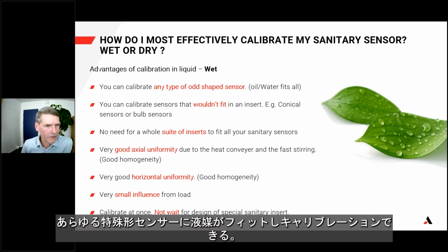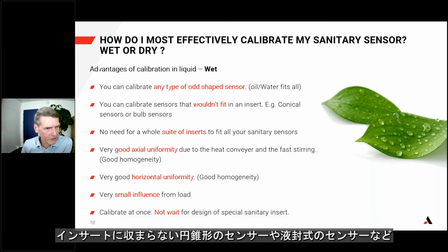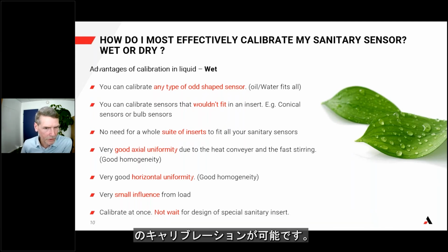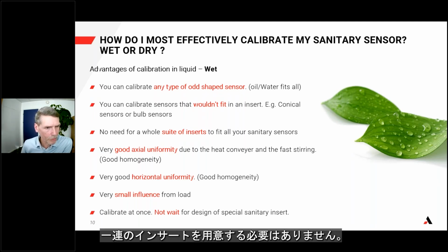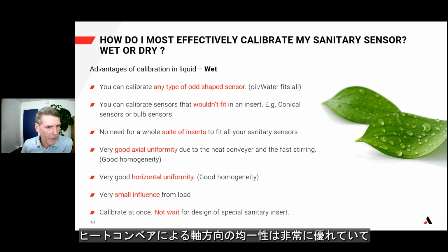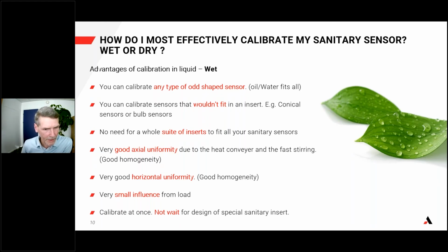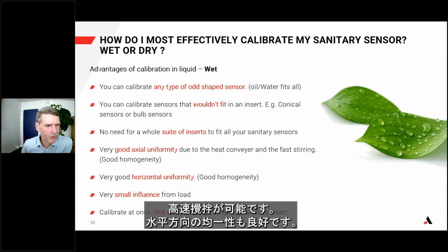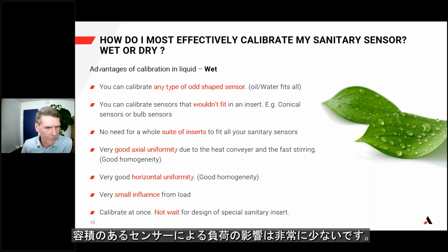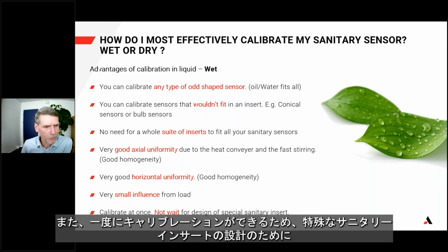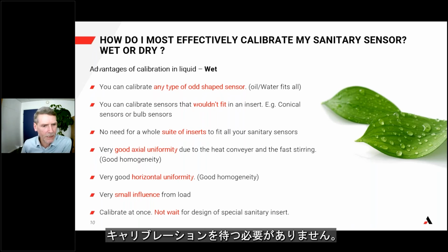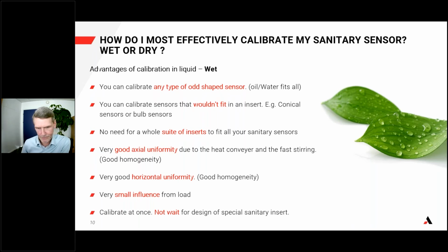You can calibrate any type of odd-shaped sensors. Oil and water fits all. You can calibrate sensors that wouldn't fit in an insert. That could be a conical sensor or a bulb sensor. You don't have to have a whole suite of inserts to fit all of your sanitary sensors. You have very good axial uniformity due to the heat conveyor and the fast stirring. Very good horizontal uniformity, very small influence from load, and you can calibrate at once, meaning that you do not have to wait for design of special sanitary inserts.